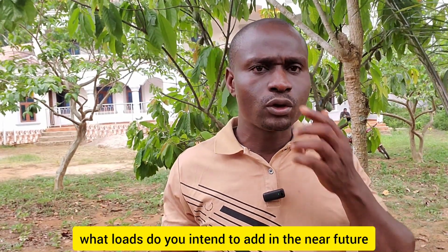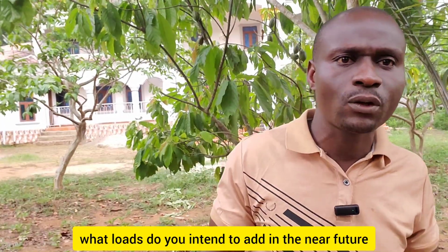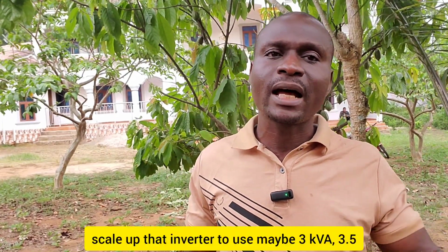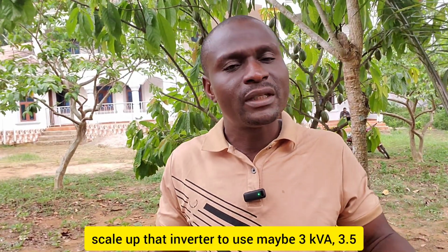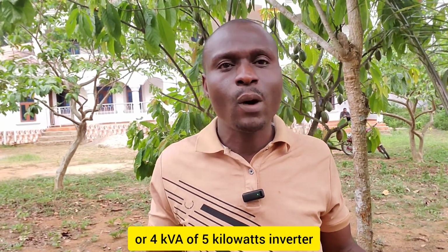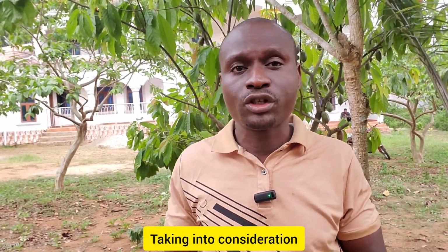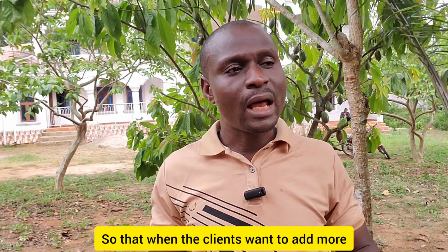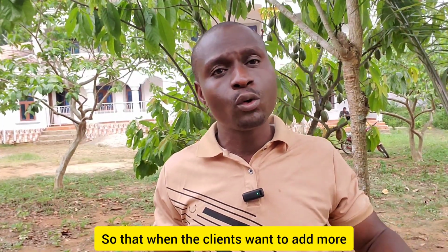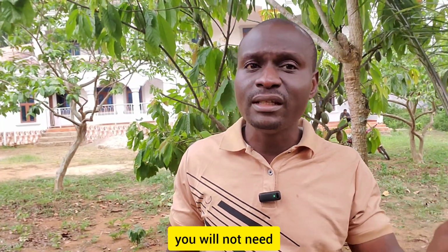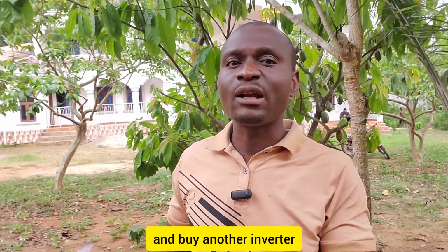You can ask your client, what loads do you intend to add in the near future? He may give you 1 or 2 loads. So you need to scale up that inverter to maybe 3 kVA, 3.5, or 4 kVA or a 5 kilowatt inverter, taking into consideration that in the future this client is going to add more loads, so that when you want to expand, the client will not need to go and buy another inverter.